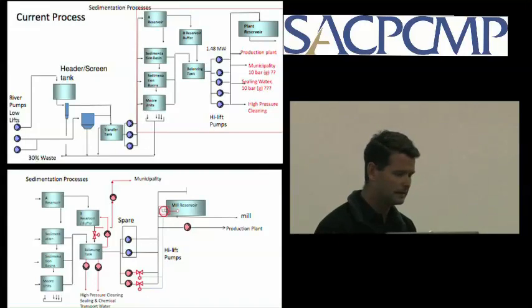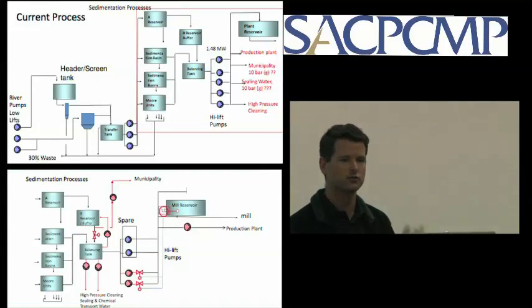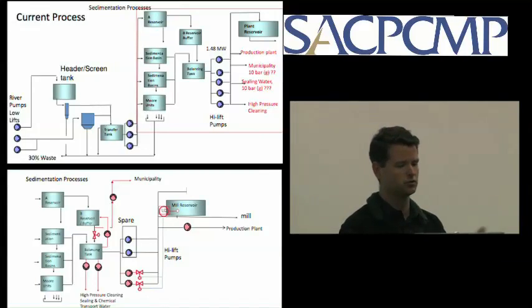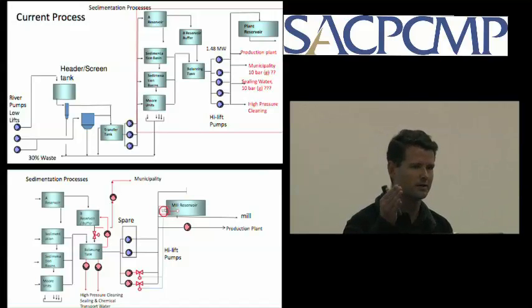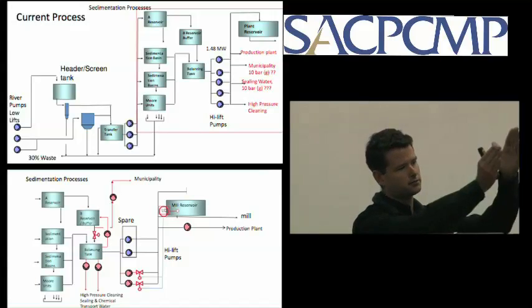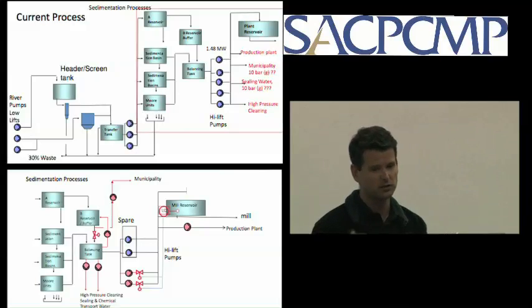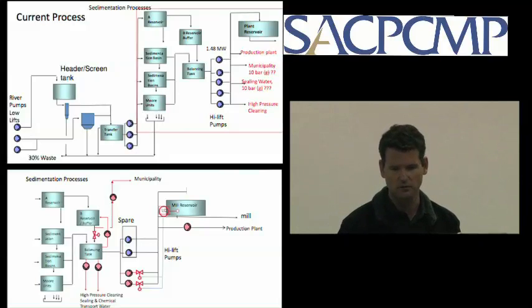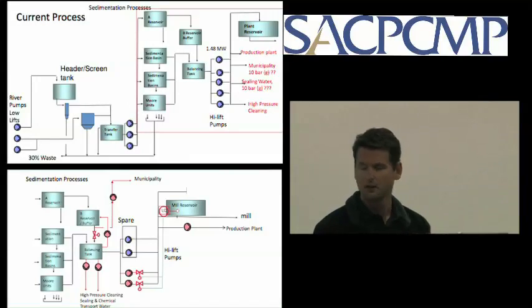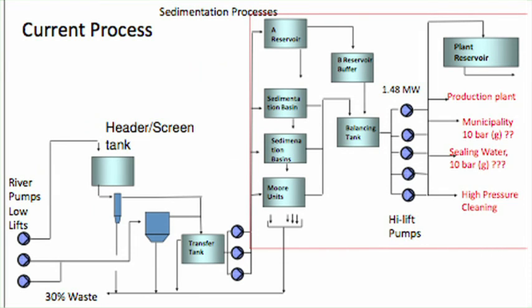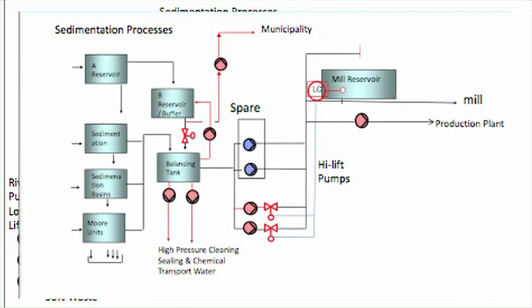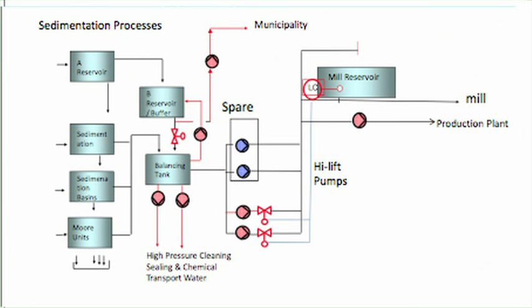So we put in a complete redundant SCADA control system, and we split the plant into streams so that if one analog card went out, the other two lines carried on running. That was another major change that we did in the plant. As I said, we upgraded one pump and put one new pump in parallel to it. These two we kept as spare, and we demolished the two to get the new pumps in. We put in a small pump using that high suction head on the B reservoir to supply the local municipality.